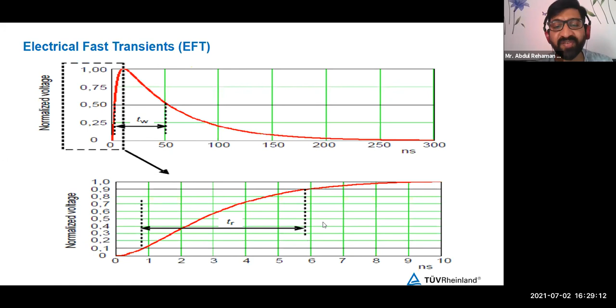Here, basically, this is the capacitive coupling clamp, where the signal lines are being tested. Usually, the signal lines will be passed through this capacitive coupling clamp, and the electrical fast transient generator is bonded to the ground reference plane. The standard defines that the electrical fast transient generator has to be bonded to the ground reference plane, so that the reflection from the GRP is captured during the testing. So basically, when we inject the noise, it is with respect to the GRP itself.